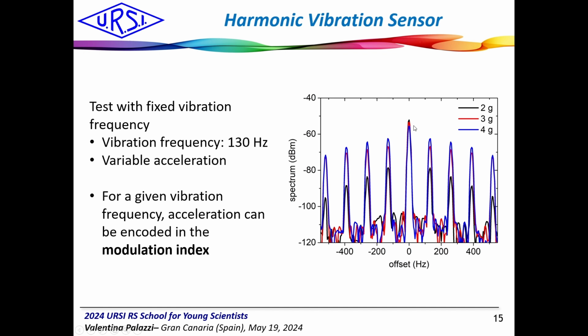If you consider the ratio between the power here and here, you can see that when you change the acceleration, you have a change of this modulation index. And by the way, you can do this because you are working at the second harmonic. So this power here is not affected by the environment, it's only generated by your frequency doubler. So this is robust information that you get.